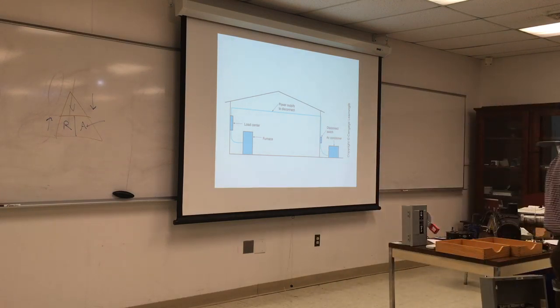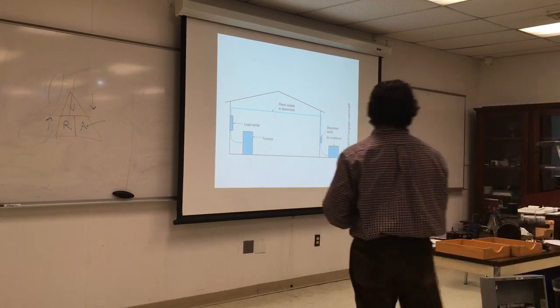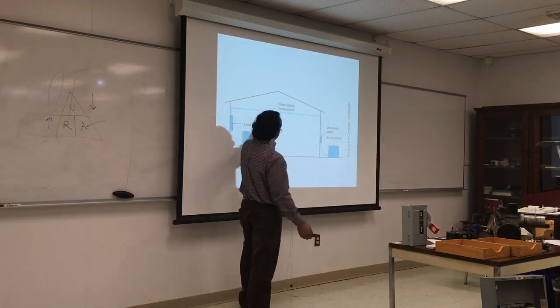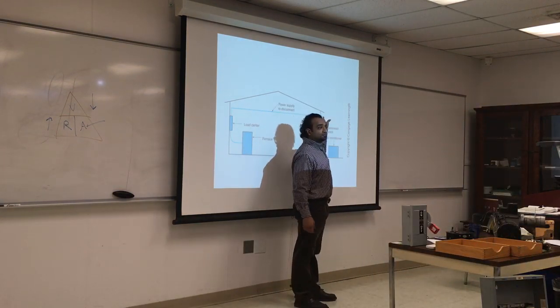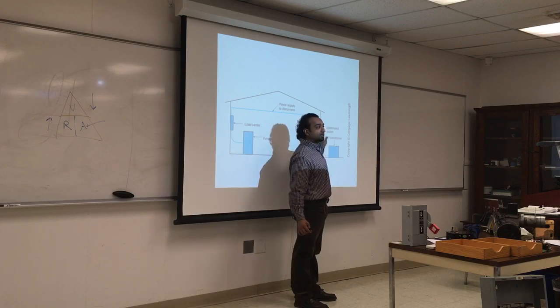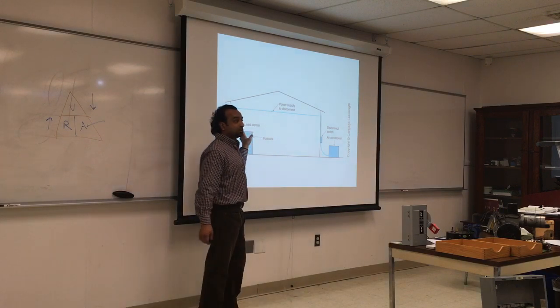Some people go to the extent of building a shelter for the compressor to protect it from leaves coming in or animals, but sometimes it's not done. So it's good to have a disconnect switch close to it. This one here, if it's within 100 feet, it should be okay. It should be included in the design of the voltage drop. If not, you should probably double check.